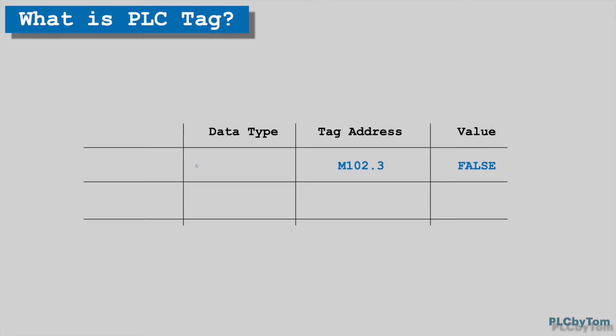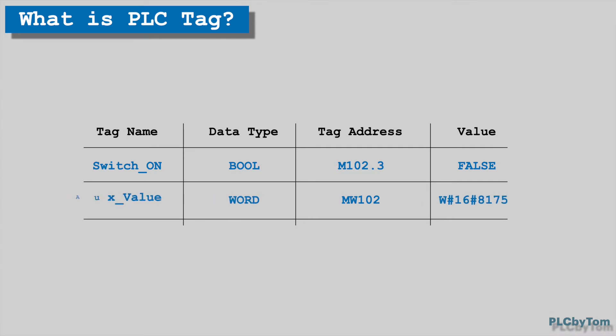Beside to this there is another thing that has to be defined for PLC tag. It is data type. By data type is defined how binary representation from memory location will be presented. Also, each PLC tag shall have a defined tag name. Tag name is generated automatically as tag underscore one, which can be renamed to be more intuitive and easy for use in PLC program. Finally we can say that the PLC tag is memory space on the CPU where values or data can be saved, and the PLC tag is defined by name, memory area, address and data type.